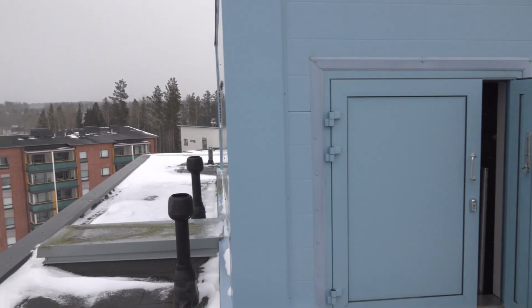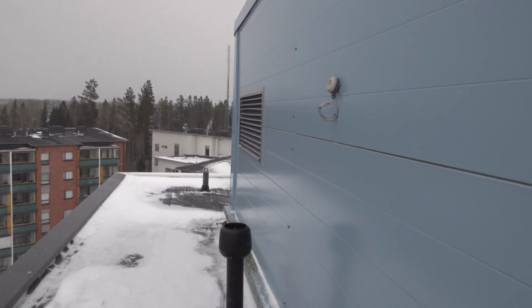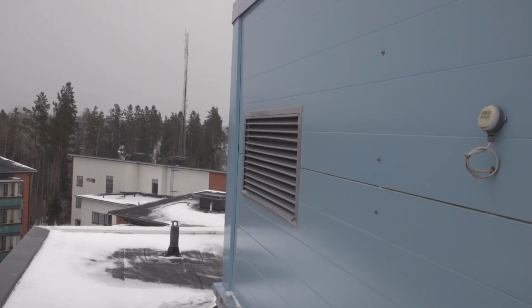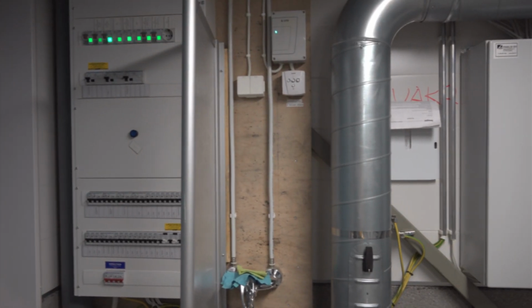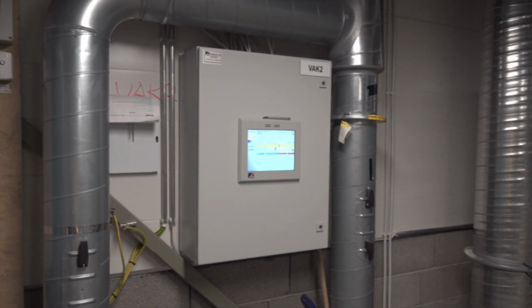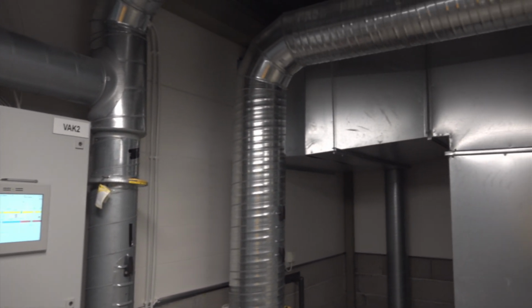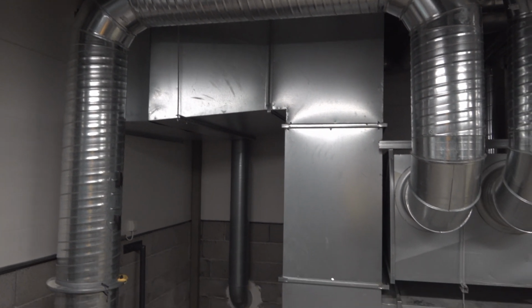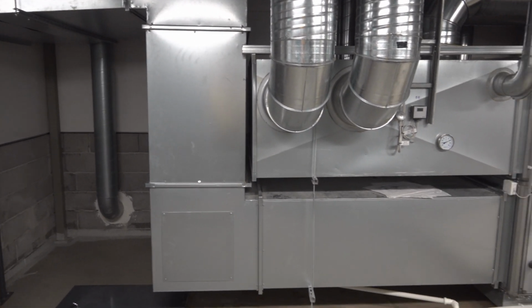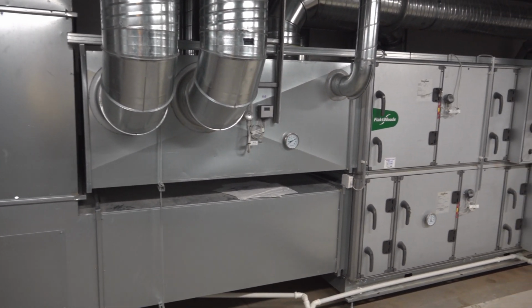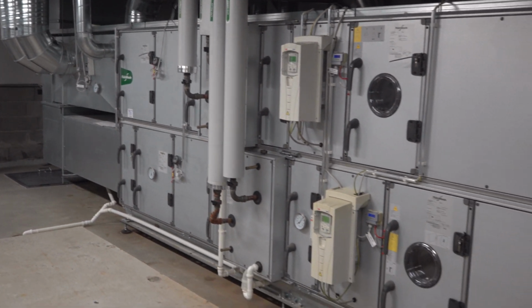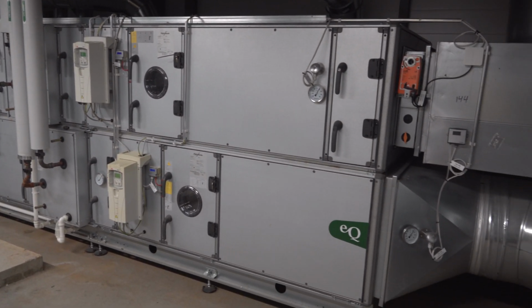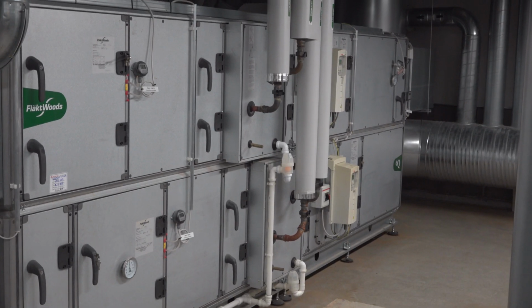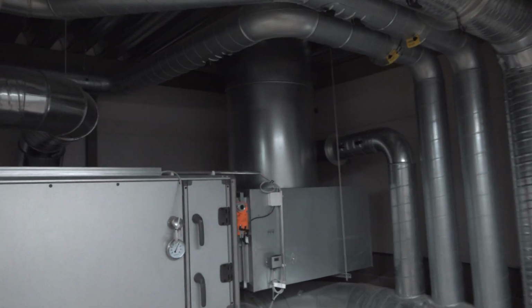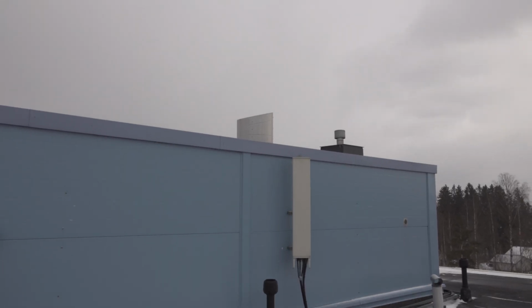Here we can see the air inlet of the whole building. The air comes in from there. The basic layout of the room is that there's a computer controlling everything in this room. There is the input channel from outside, which goes under the collector box for the exhaust air. There's some thermometers, and then there's the ventilator split into two upper and lower parts, which contains all the technology like the heat exchanger itself, plus fans and filters and shutters. And then there's that tube going to the roof, which is the exhaust.